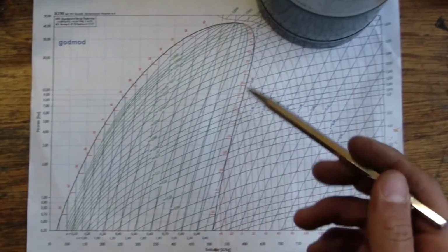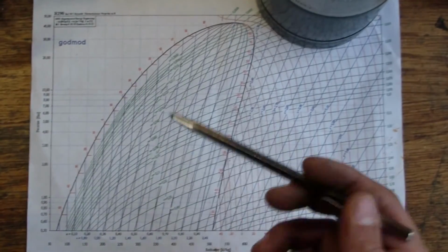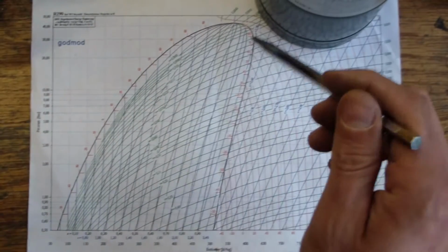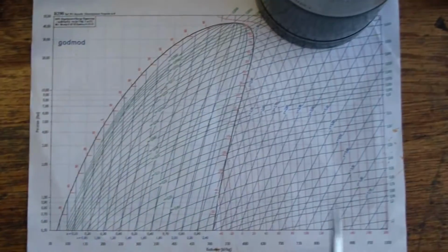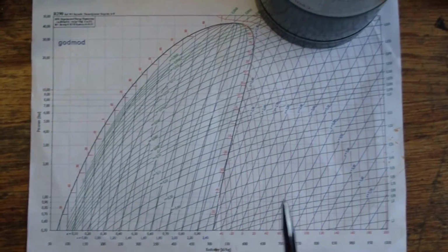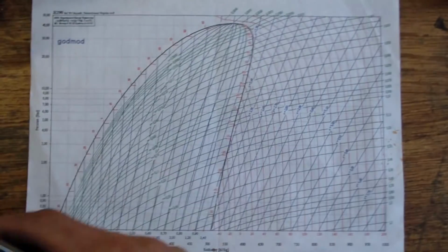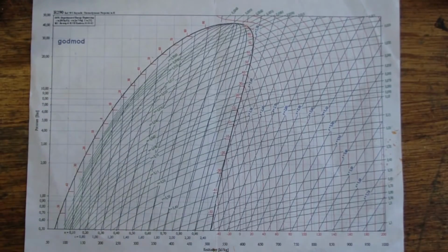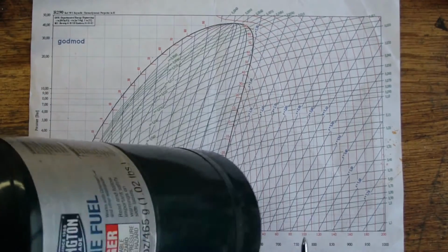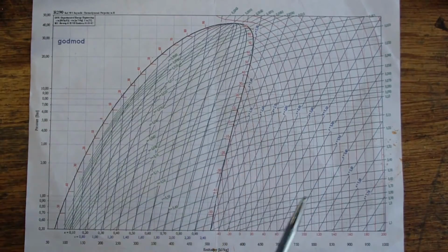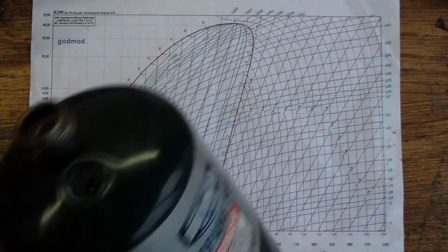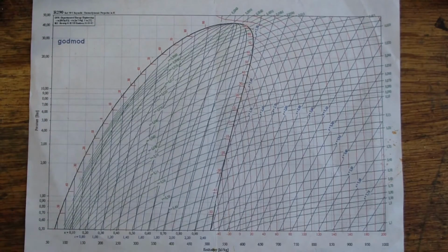And then the opposite is true. If we lower the temperature in the shop and it gets down to 50 degrees in here, we're going to get more condensation. We're going to start to travel in this direction. So this can be really useful for looking at a refrigerant system, because if we're not just looking at a simple tank, for instance, if we were to just vent some of this propane off and lower the pressure, we know from common experience and from reading our refrigeration texts that the temperature is going to drop.